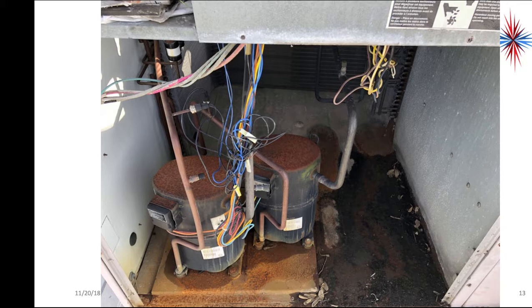Pull the unit open, the compressor cover. This is what I see. Okay, so it's a 2-circuit system, so I have a Y1 and a Y2 with 2 compressors. Pretty rusted out. Again, age and relationship to salt water of this equipment. Really, it's not unexpected what I'm seeing here. Okay, note this big ball of wire here, because we're going to get back to that. The big ball of wire is all the control voltage for the pressure controls.